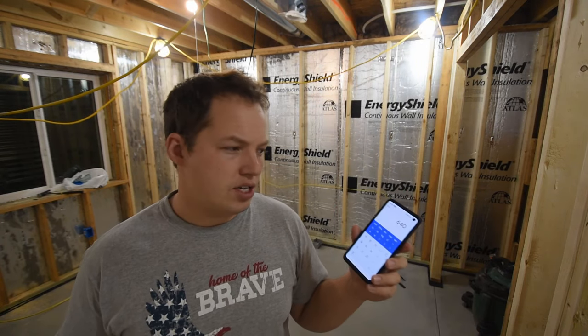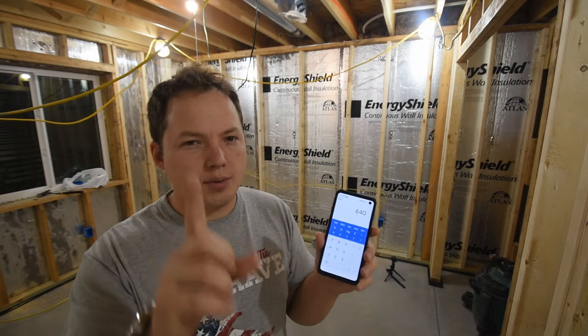So we can see that with our roughly 200 square foot bedroom, we're not going to come anywhere close to using up the total available square footage for one 20 amp circuit of 640 square feet. So we could actually do two more bedrooms in addition to this one on one 20 amp circuit. Now before you go and absolutely max out your circuit and put as many square feet on one as you can, I have one suggestion for you.